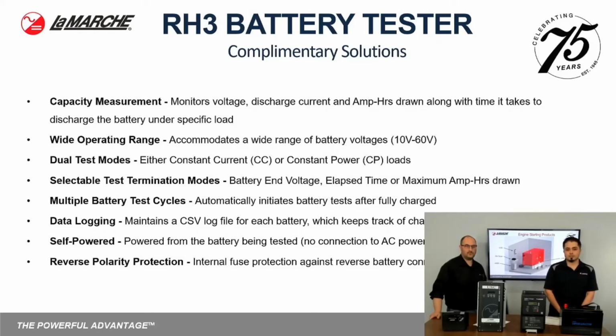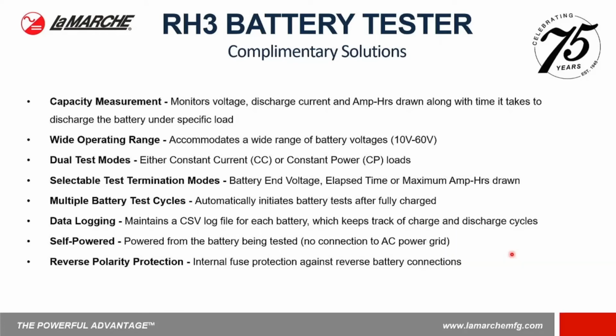Selectable test terminations being a battery end voltage, maybe in regards to protecting the battery, not getting down too low. Elapsed time or a certain duration, or maximum amp hours that was taken out of the battery itself. Different battery test cycles can be done automatically. Obviously, they can be done in your daily or your weekly, even monthly cycles. And your data logging is available through an Excel file or a CSV Excel type file, where you can easily track those changes or those trends of your charge and discharge cycles.